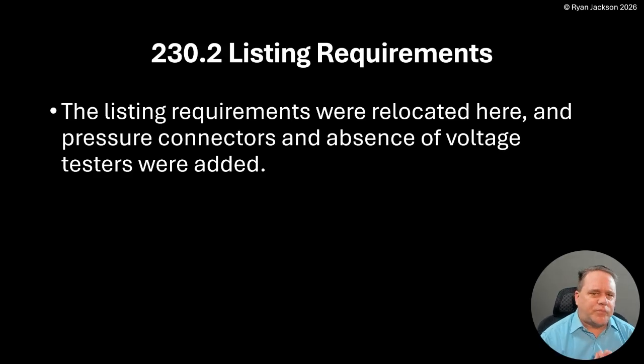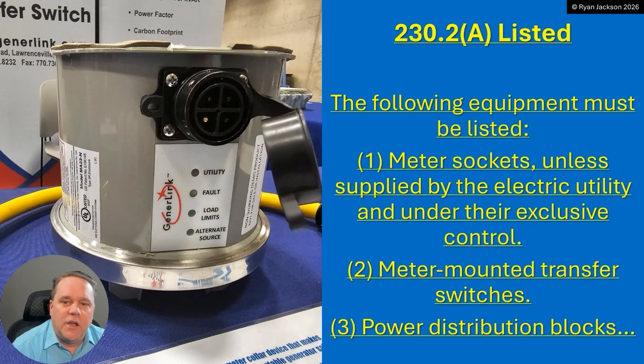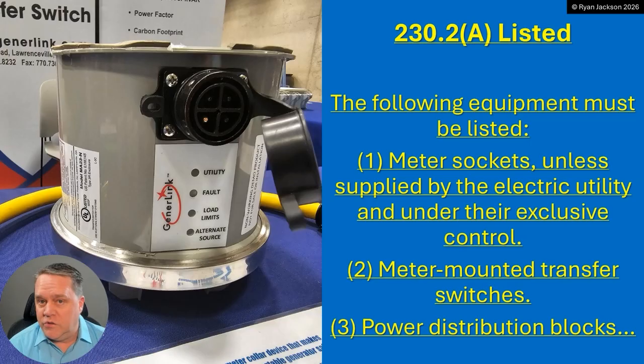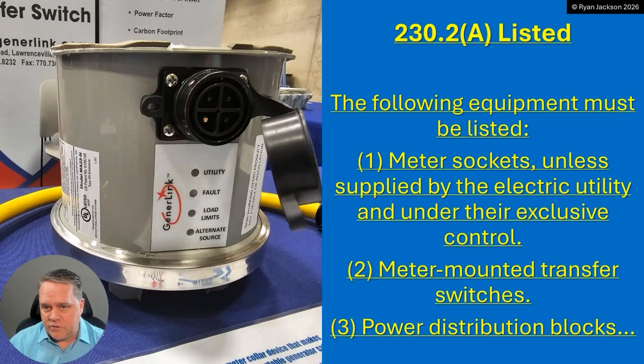Article 230, Section 230.2, Listing Requirements. The listing requirements were relocated here. In the 2026 NEC, they made two global changes to basically reserve the .2 section and the .3 section in every article. Articles are always whole numbers — Article 230, Article 406, Article 480. Sections are the decimals, so 230.2 is a section, 408.6 is a section. In almost all of the articles, the .2 section is reserved for listing requirements, and the .3 section is reserved for reconditioning requirements.